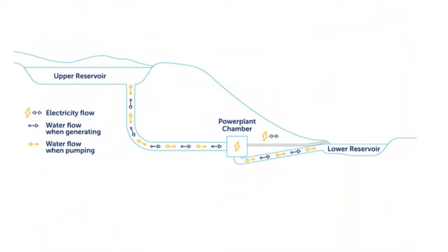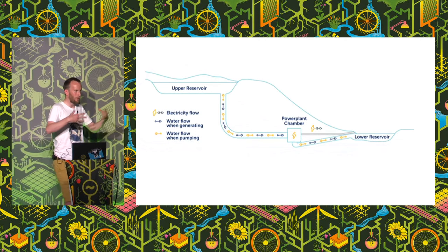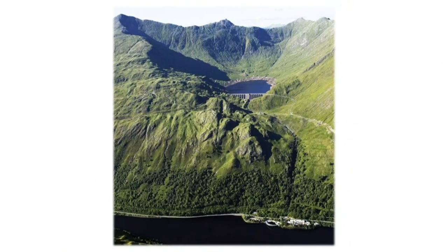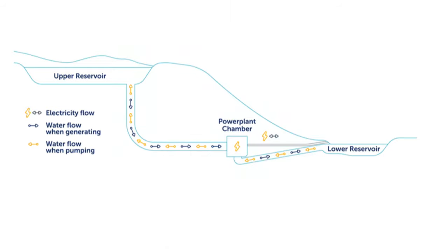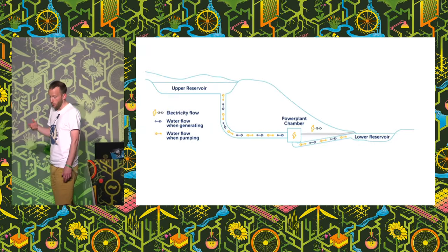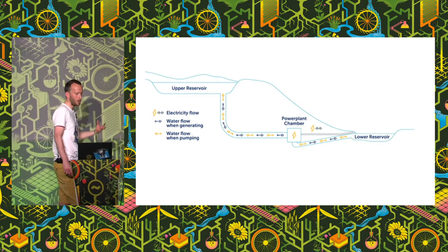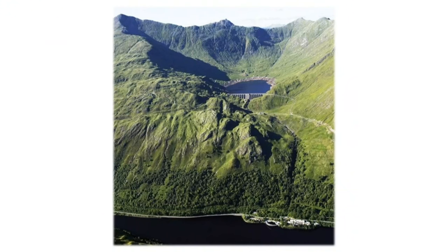So we're quickly going to talk about pump storage, which really is the future for hydro in Scotland. We've had a long time where there was no investment in hydroelectric infrastructure. But now that we have all these renewables connected to the grid, we need a way to store this energy. Pump storage still really is the only way to store large amounts of energy that you can access quickly and connect to the grid. As a point of reference: Cruachan, which is our biggest pump storage scheme currently in Scotland, has 6,600 megawatt hours of stored energy. Our biggest grid-connected lithium battery is down at Pillswood, and that's only 198 megawatt hours — so 33 times more capacity even in a small pump storage scheme. Pump storage is when you're pumping water uphill at nighttime or when you've got excess energy, and then letting it flow back downhill when you actually need to capture the energy.